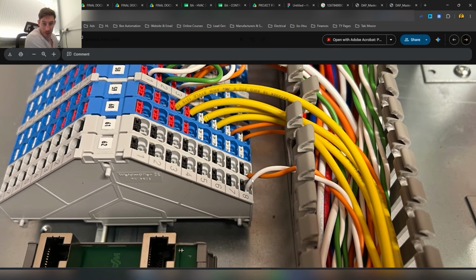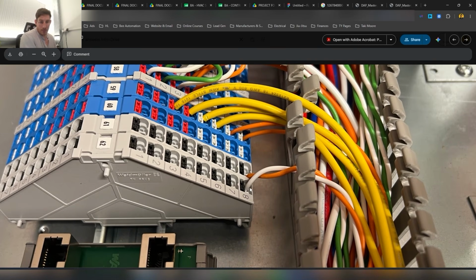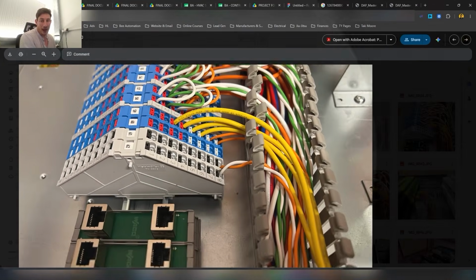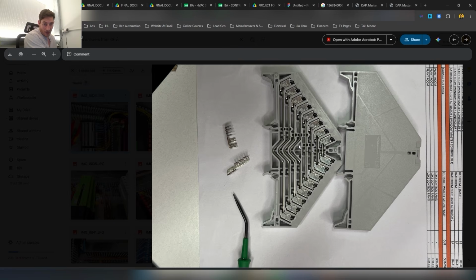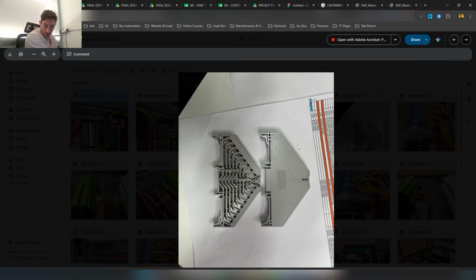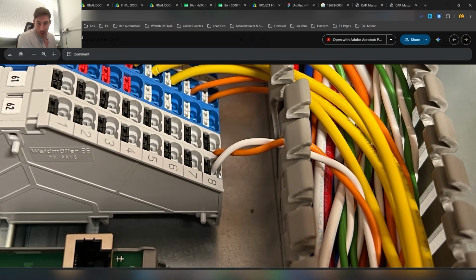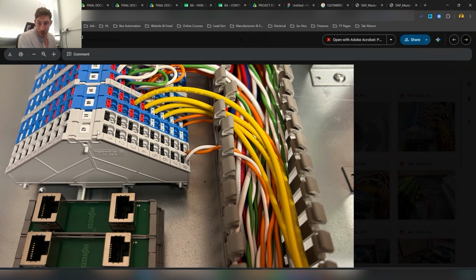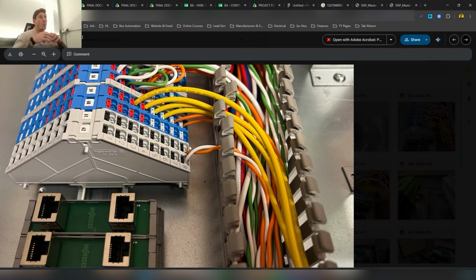So there's that 24 volts being distributed out. So what I mean is, we've kept them intact, so these connections are in. If we've got 0 volts on this side, every terminal has 0 volts on it. So we can put multiple cables into 62 and it'll be 0 volts, and multiple cables into 61 and it's the positive 24 volts. It's just a way of distributing quickly and easily with multiple points to go into your 24 volt DC.